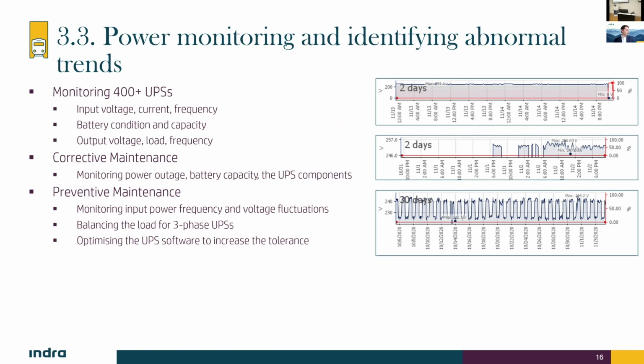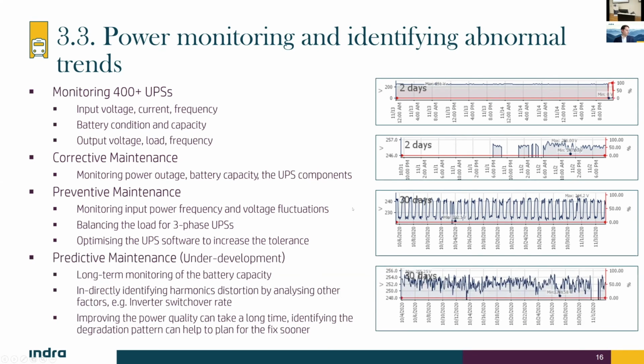For preventive maintenance, we use this data to, for example, distribute the load between different phases, or increase the efficiency of the software controlling the UPS. The interesting part is predictive maintenance - another project we're working on. The goal here is, for example, for batteries: they can lose their capacity over a long time. In 2 years, the capacity of your phone battery can go down to 60%.